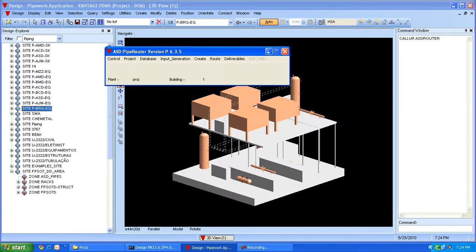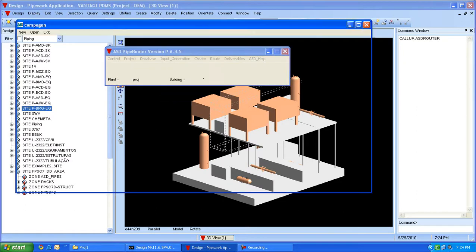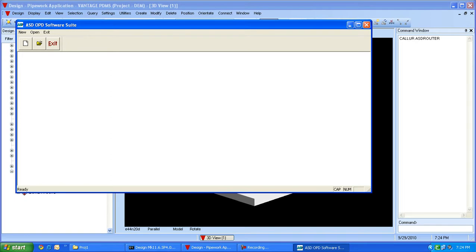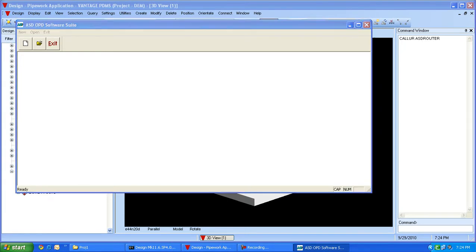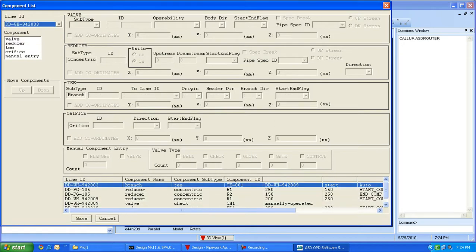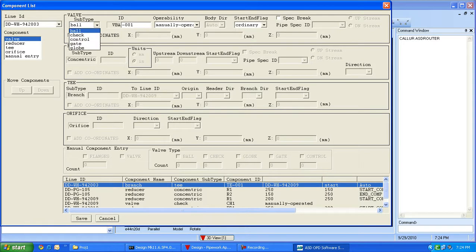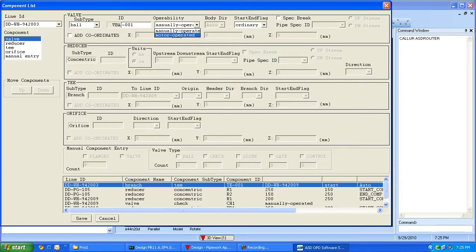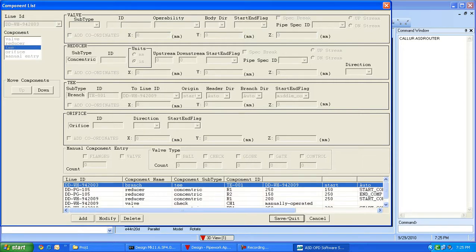The next step would be to enter the components for the lines. You can add a component for any line through our component list template. This template is linked to our line list directly and lists all lines in the drop-down menu. We can select a line and a component that needs to be placed during routing. These are the types of valves — manually operated or motor operated. We can also decide whether valves should be placed at the start or end, locate the valve by giving exact 3D coordinates, and save it. Similarly, other components like T and reducer can be added through the component list.